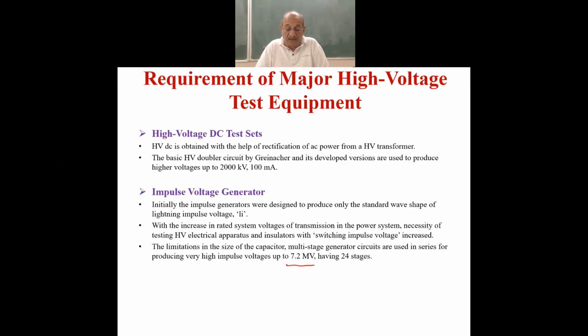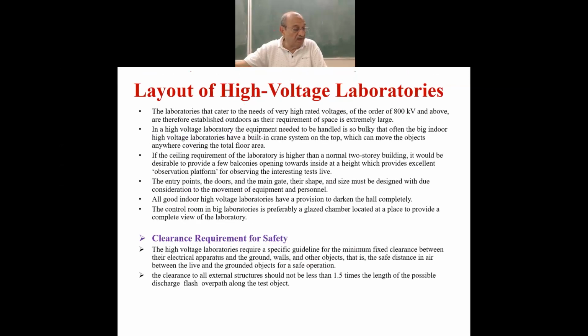That 7.2 may have 24 stages if each one is having 300 kV, and if each one is having 200 kV, 36 stages may be required. There is a possibility to go for a single stage up to 300 kV. So this is how the impulse voltage generators in the high voltage laboratories appear to be. Now let's talk about the layout of the laboratories.